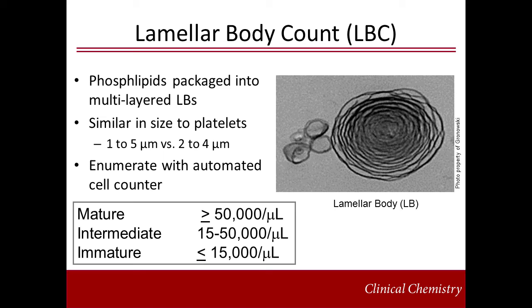Lamellar bodies are packages of phospholipids that are made by the type 2 pneumocytes in lung alveoli. The most recent fetal lung maturity test was developed in the mid-1980s when it was noted that lamellar bodies were similar in size to blood platelets and could be enumerated using an automated cell counter. Lamellar body count testing is a laboratory-developed test. A hematology analyzer is used to analyze the amniotic fluid in the CBC mode and the lamellar bodies are counted as platelets. Lamellar body counts of 50,000 per microliter or greater suggest pulmonary maturity. However, results are instrument dependent and need to be validated in individual laboratories. Test results are affected by blood and meconium when present in amniotic fluid.